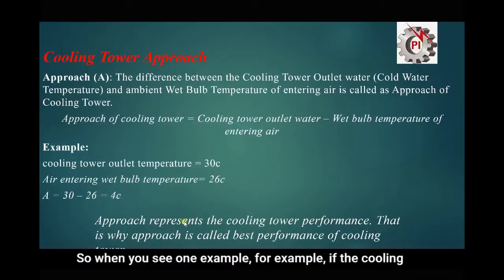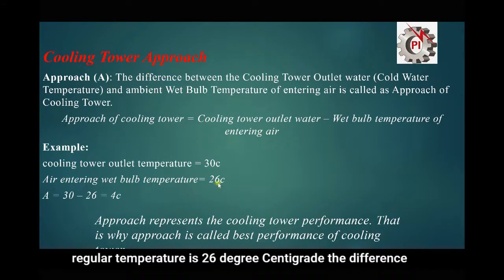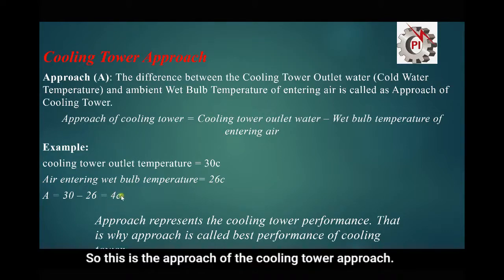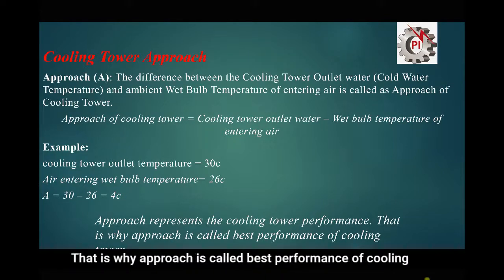For example, if the cooling water outlet temperature is 30°C and the entering air wet bulb temperature is 26°C, the difference is 4°C — so this 4°C is the approach of the cooling tower. The approach represents the cooling tower performance, and that is why approach is considered the best indicator of cooling tower performance.